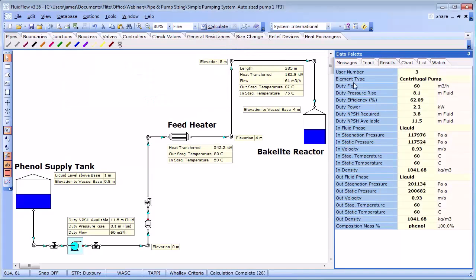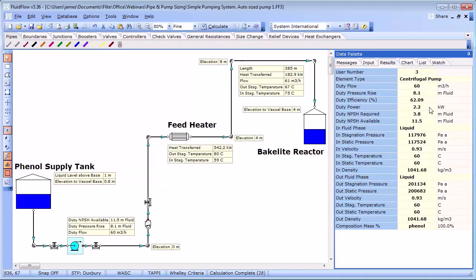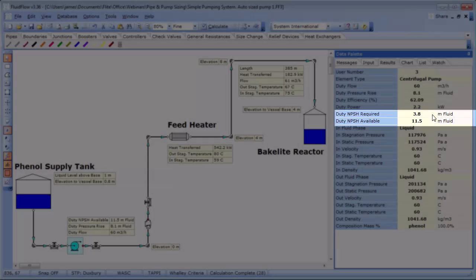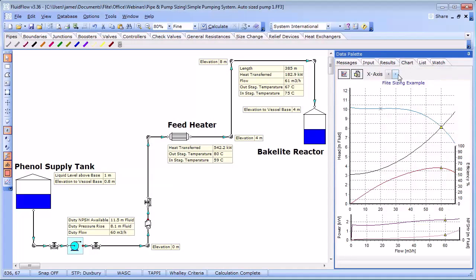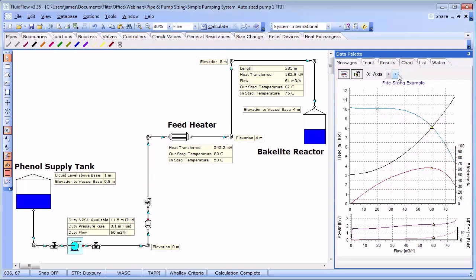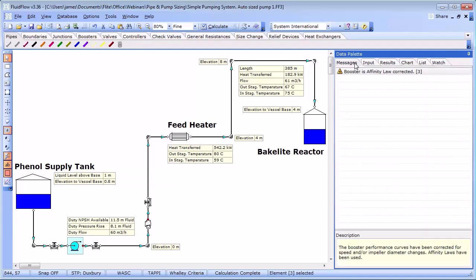Let's set about increasing the pump speed to match our design requirement. If we increase the pump speed to 1871 rpm the duty flow now becomes 60 meters cubed per hour with a subtle increase in duty pressure rise to 8.1 meters of fluid. The duty efficiency is 62% and the duty power is 2.2 kilowatts. A quick check on the NPSH conditions confirms that we are still within the safe operating limits for the pump. We can also make a quick check on the pump curves to review the performance. You may also notice that we have a warning message. This is just letting us know that the booster affinity laws have been applied since we have changed the pump operating speed.